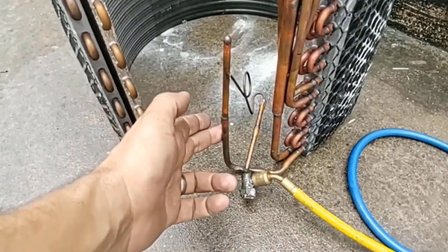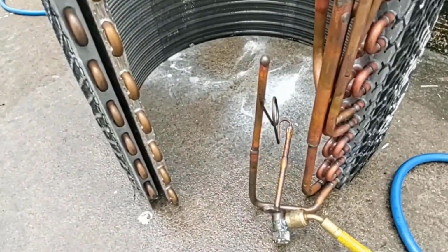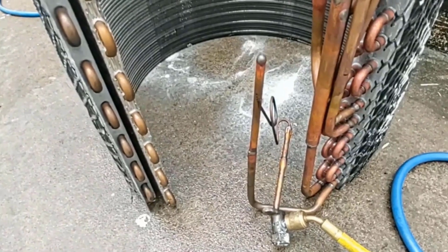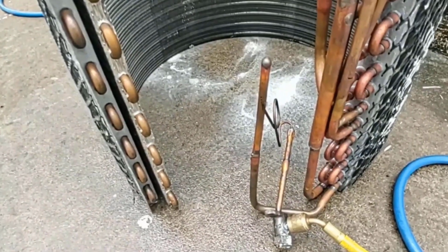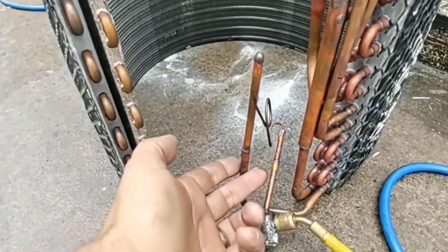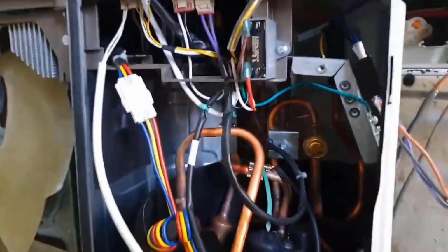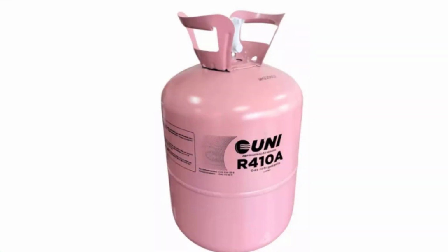Now, if you are a technician and you have come across this problem, what should you do? First, check the capillary to make sure it is not obstructed. It is also important to check the condenser temperature sensors, both the one near the grid and the immersion sensor in the coil, to make sure they are all working properly. Then, check if there is any obstruction in the coil and if the gas is leaving the compressor properly, measuring the compressor outlet pressures and ensuring that the gas flow is normal.